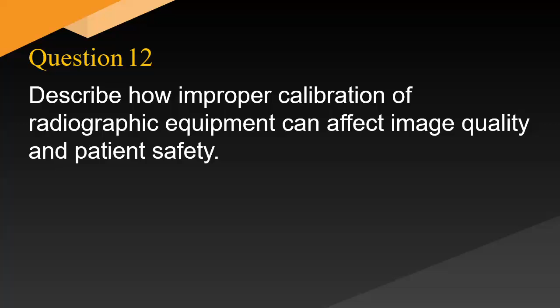Describe how improper calibration of radiographic equipment can affect image quality and patient safety. Answer: improper calibration affects both image quality and safety. Image quality: overexposure leads to loss of detail due to excessive density. Underexposure results in grainy images due to insufficient X-rays. Misalignment of the beam can create artifacts and uneven exposure.